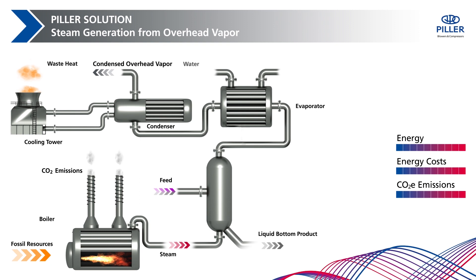Process boiler feed water or condensate from any process can be used here. The required steam is generated at a relatively low pressure and temperature level. Process waste heat is used as the heat source for generating the steam, and the thermal energy is transferred to the water by condensing the overhead vapor. This form of heat transfer has major advantages: compared to other fluids, water has a very high heat of vaporization and can be integrated into the existing infrastructure.